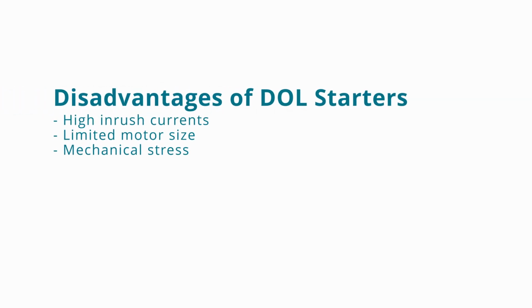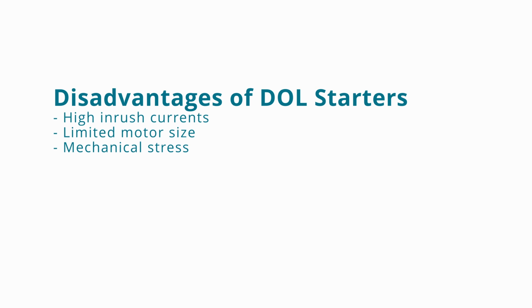Now, let's discuss the disadvantages of the direct online motor starter. The first one, obviously, is the high inrush currents, which cause significant voltage drops on the power supply with the potential to cause damage to electrical equipment. The second disadvantage is the limited motor size. And the third one is mechanical stress. Starting your electric motor at full torque and stopping abruptly without decelerating gradually causes bearings to wear out faster.